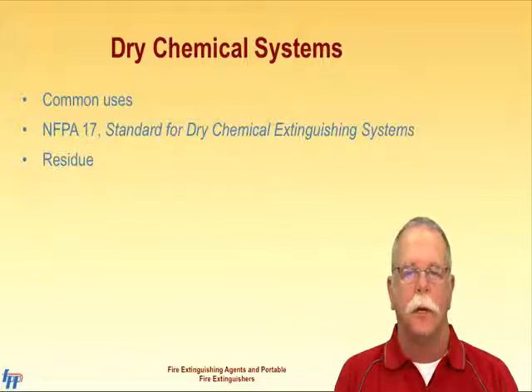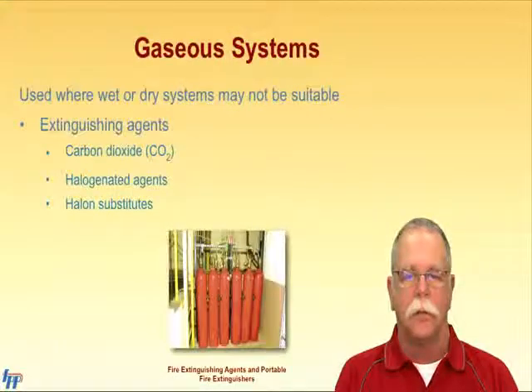Dry chemical systems may be used to protect flammable or combustible liquids and gases, dip tanks, paint spray booths, exhaust duct systems, commercial cooking installations, transformers, marine applications, heavy diesel equipment such as earth movers, excavators, etc. These systems discharge a cloud of extinguishing agent that leaves behind a residue that creates a significant cleanup for the entire area, even that which was not involved in the fire. Furthermore, dry chemical systems are not recommended for areas of sensitive electronics as the residue is quite corrosive.